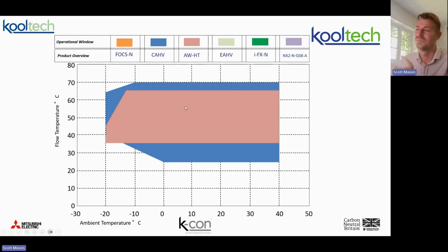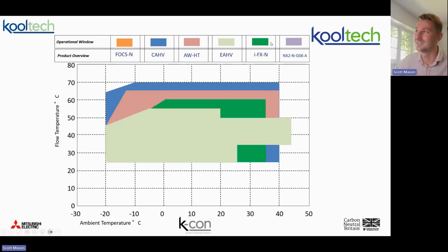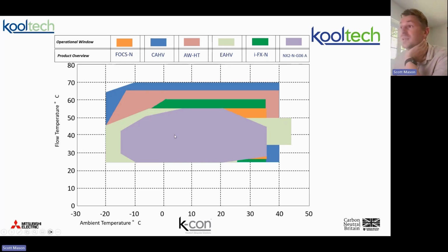But you see what I mean, this is quite a basic unit. It's going to produce your heat, but because it's a high GWP refrigerant, it's actually got quite a good operating window when compared to low GWP alternatives. In fact, it's the second best, if you will. So that's a big consideration. We're always going to want to make sure that whatever your building is doing, the curve lands within an operating window for a unit.